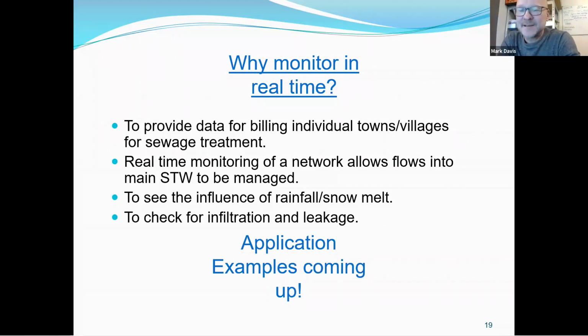Something I would also add, the application example where we had 3 months running on the fuel cell is really a good illustration of what would happen with winter here. Because if we combine that with a solar panel for the summer months where we have good light, it would basically mean that you would only have to revisit a site potentially once a year just to change the fuel cartridges.